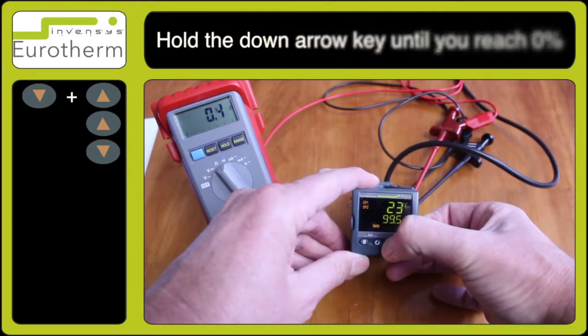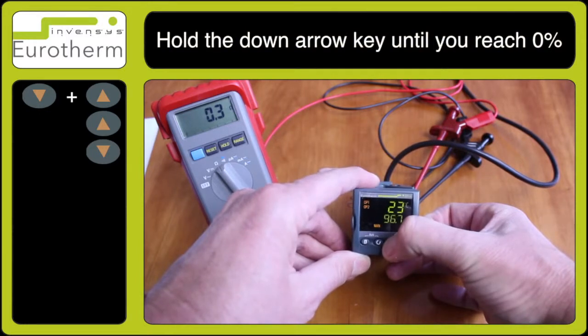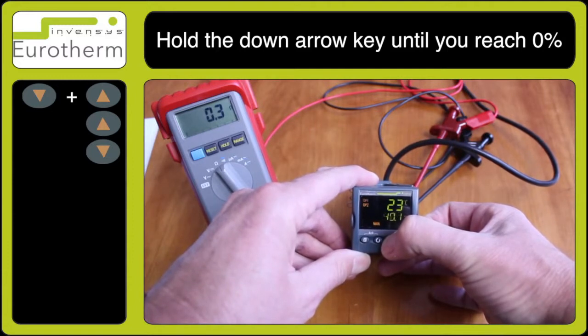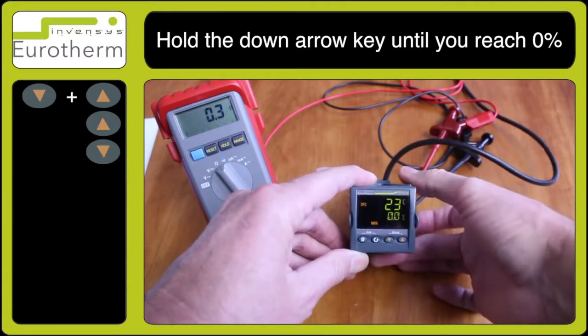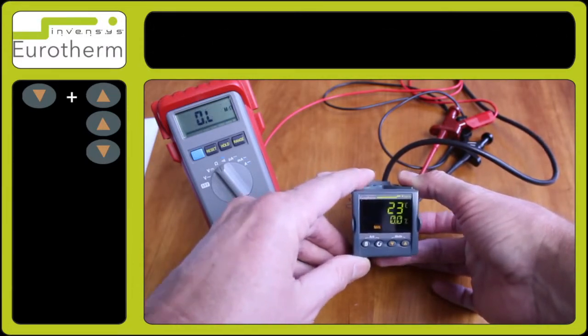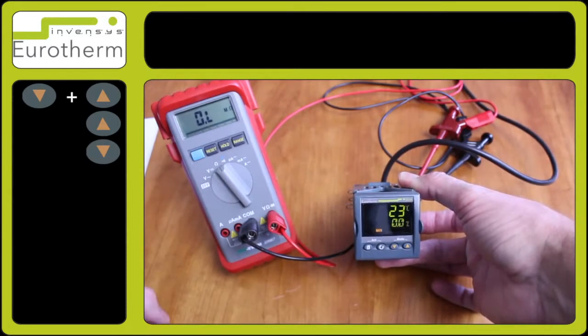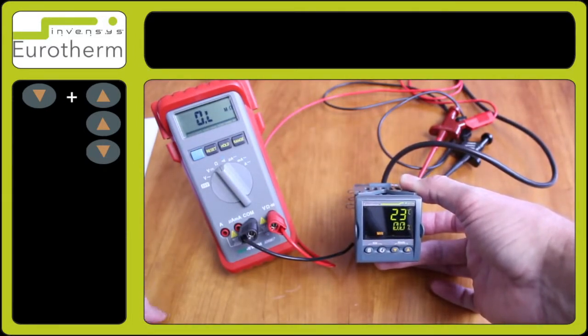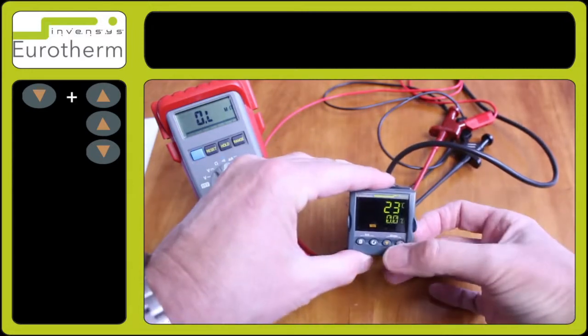Using the down arrow key we can ramp down to 0% like so. Once that's entered the relay will now switch over and my multimeter has now gone to open circuit. So that is how you test the relay output.